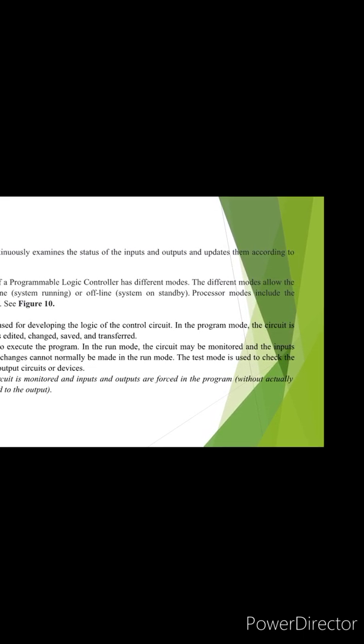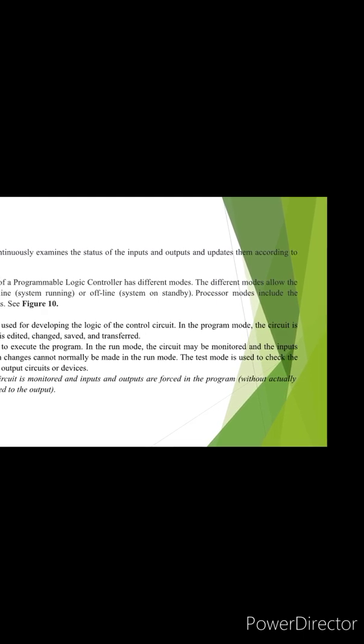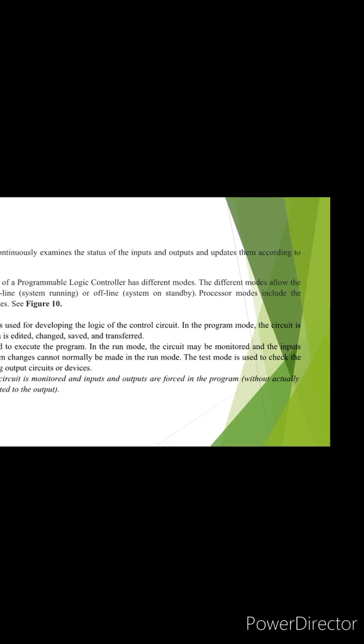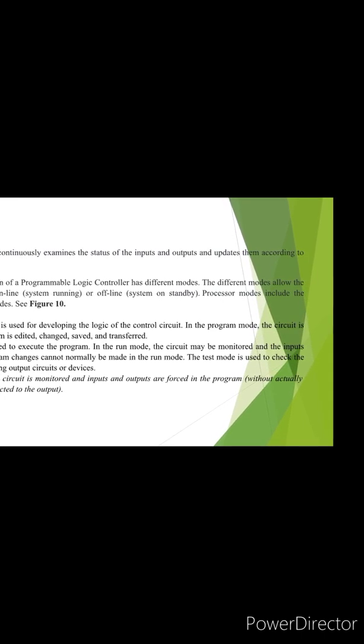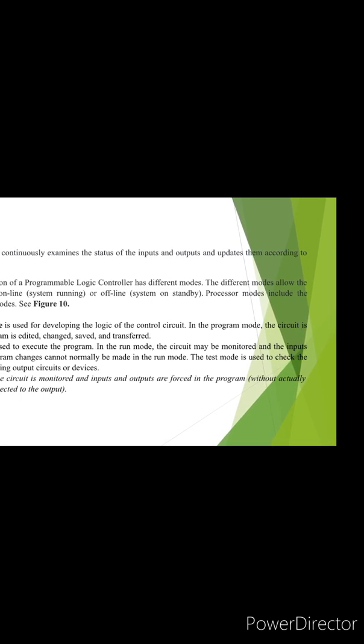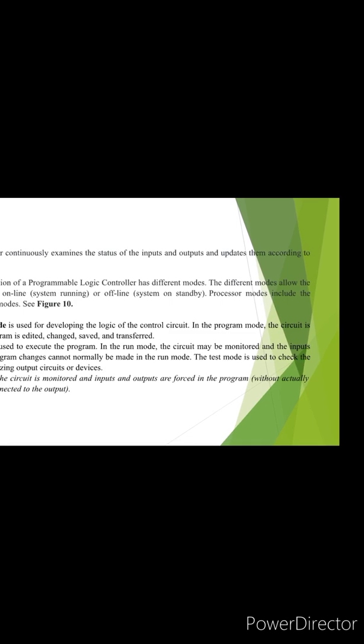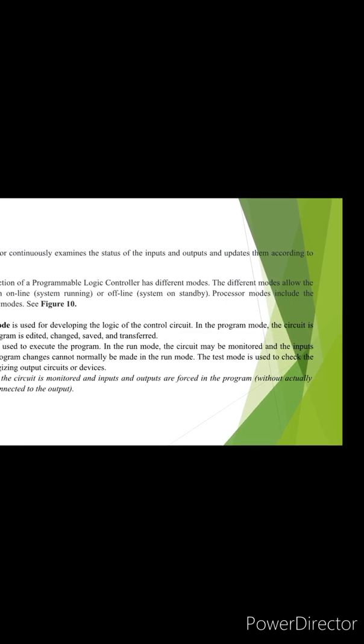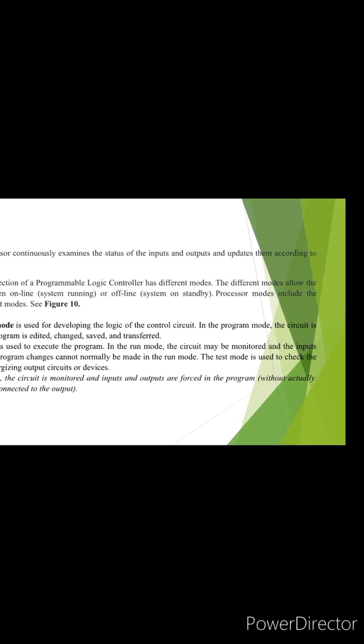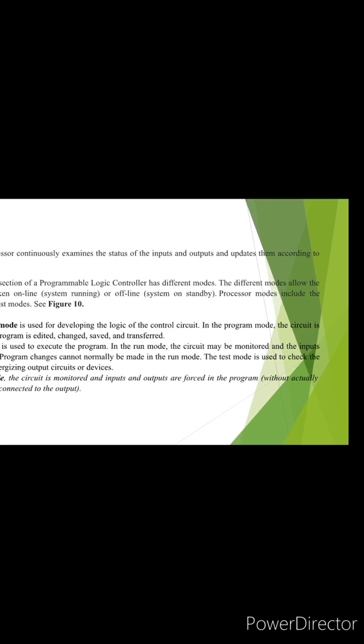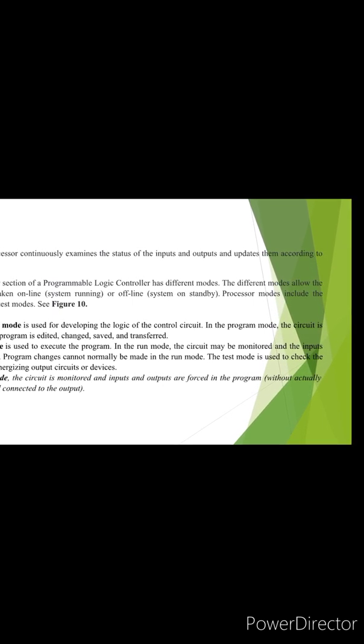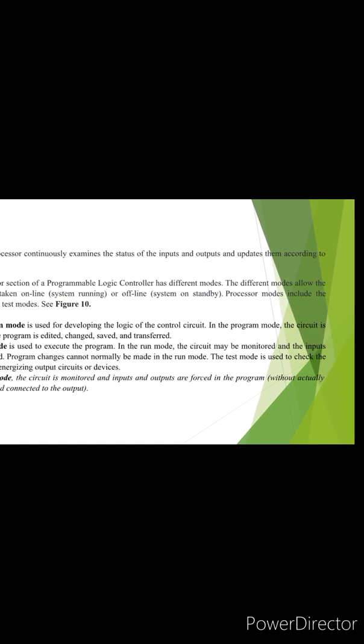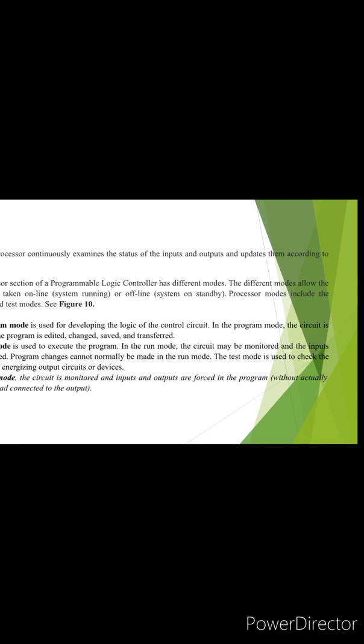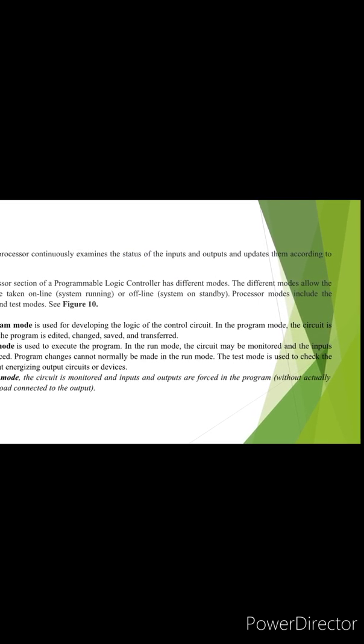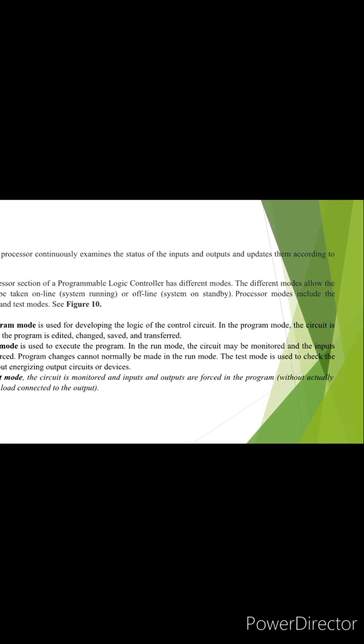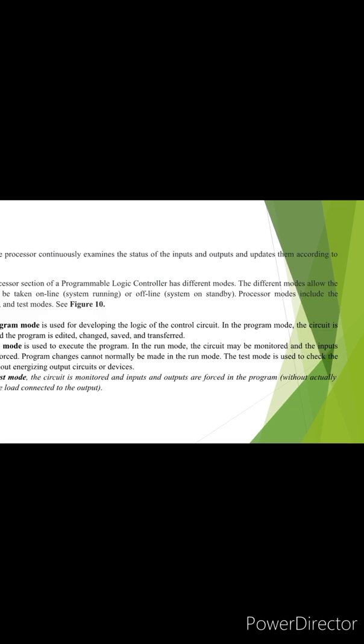Processor modes include the program, run, and test modes. See Figure 10. The program mode is used for developing the logic of the control circuit. In the program mode, the circuit is monitored and the program is edited, changes saved and transferred. The run mode is used to execute the program. In the run mode, the circuit may be monitored and the inputs and outputs forced, but program changes cannot normally be made. The test mode is used to check the program without energizing output circuits or devices. In the test mode, the circuit is monitored and inputs and outputs are forced in the program without actually energizing the load connected to the output.